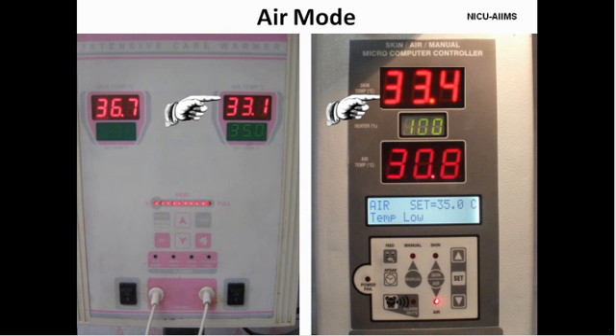An important point to be remembered is that the air temperature probe senses only the air temperature. So, in air mode, the heater output regulates according to the air temperature and not by the skin temperature of the baby.